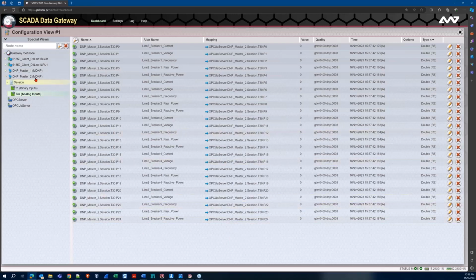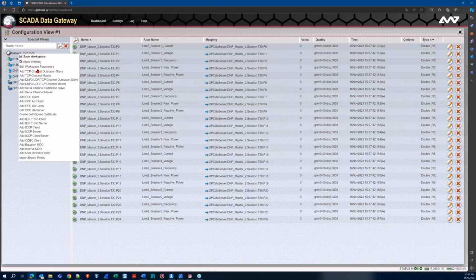But every time I bring in a point from one of these 61850 devices or DNP devices, I am adding it to a local OPC UA server. That's great, but a lot of times we also have customers that want to bring in data from an external OPC server. And in this case, we do need a local OPC UA client. So that's pretty easy to do, much like I did for my DNP and 61850 devices. I start by right-clicking on the gateway root node. Now, again, I'll skip over the TCP channel section as well as the 61850 channel section, and instead I'll come to the OPC UA area right here in the middle.